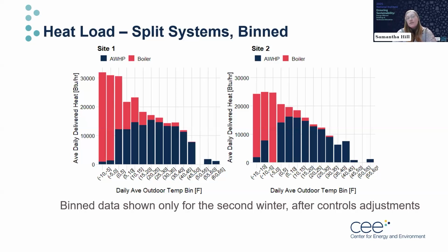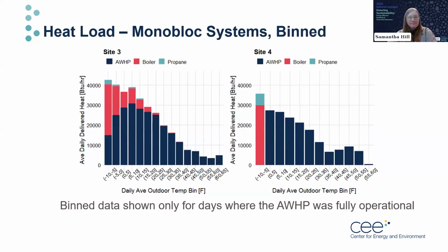The controls for these third-party split systems are relatively simple, so we did see sometimes boiler operation during temperatures where the heat pump should have been able to supply the entire heating load. And that is a function of the fact that the controls were set up to prioritize the speed of meeting set point rather than efficiency.